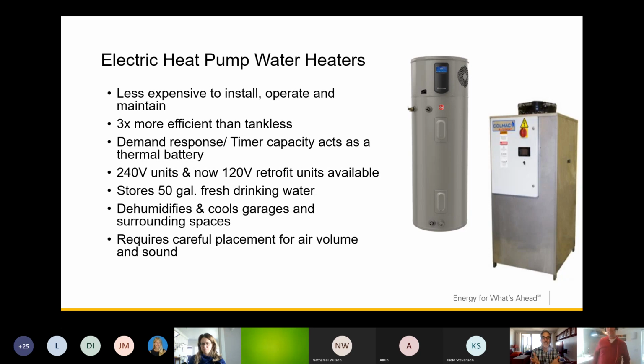Awesome. The refrigerator is a heat pump, right? It takes the heat that is in the box, that insulated box, and it throws it on the floor at your feet. And that's why it's warm down there at your feet, because it's taking the heat out of the box and throwing it on the floor at your feet. The heat pump hot water heater works the same way, but it takes the heat out of the room that it's in and throws it into the water at a very, very high efficiency.